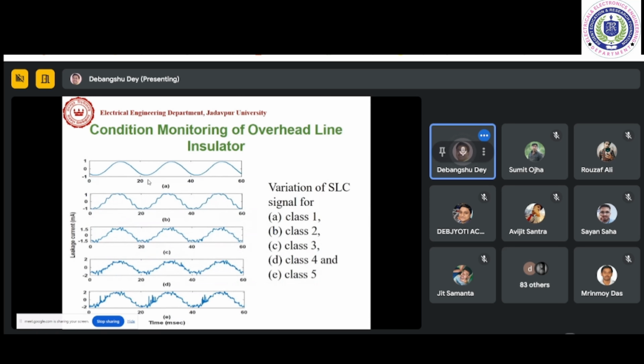The signals we record are the surface leakage currents. From a very smooth sinusoid, whenever contamination occurs, harmonics appear in the signal. So we try to find very accurate identification of the progression, whether it is between class 2 and class 3, or class 4 and class 5, and so on.